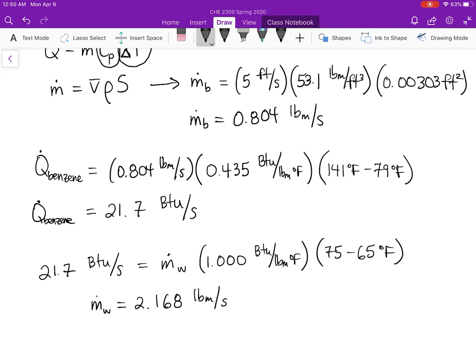So then we take our 21.7 BTUs per second, that is equal to m dot water multiplied by the specific heat of our water, which is 1 BTU per pound mass per degree Fahrenheit, and then the temperature drop of our water, or temperature increase — we're going to write it as a temperature drop. I could make this negative, but I'll just leave it positive and switch my temperatures around. Solving that equation for the mass flow rate of water, I get a mass flow rate of 2.168 pound mass per second.